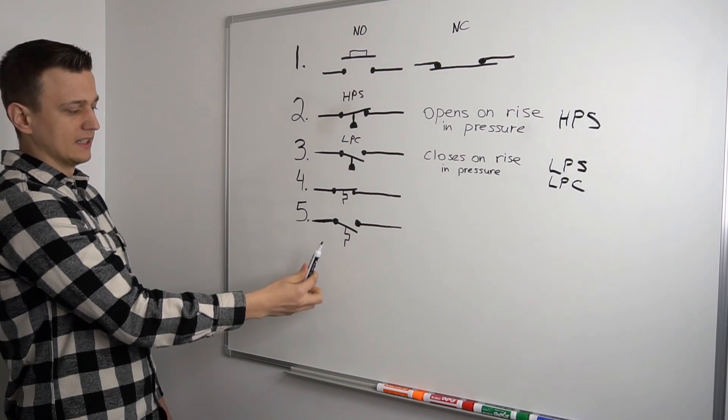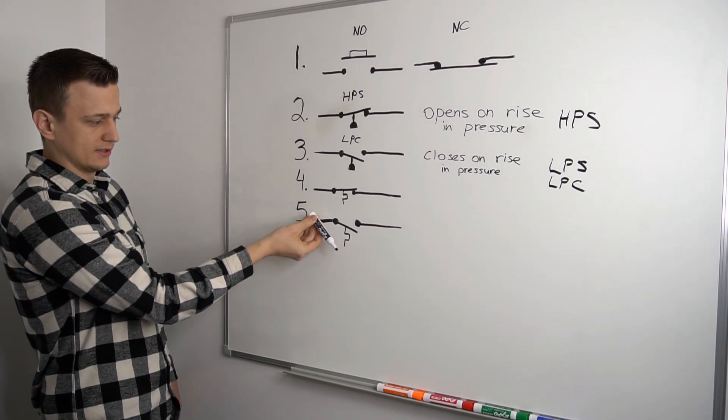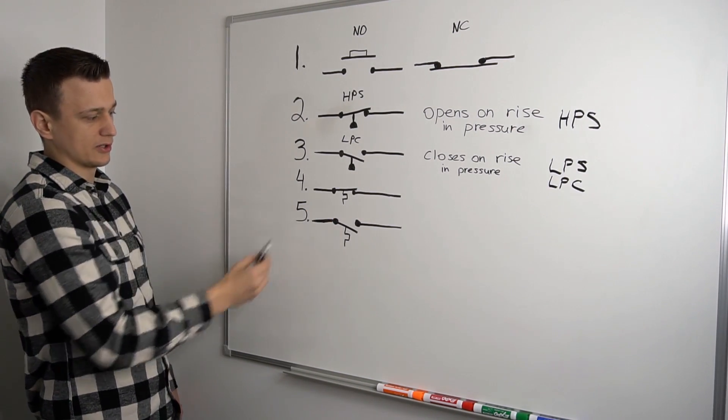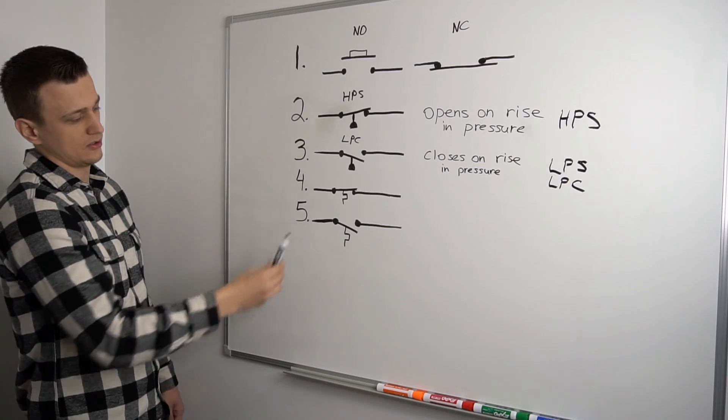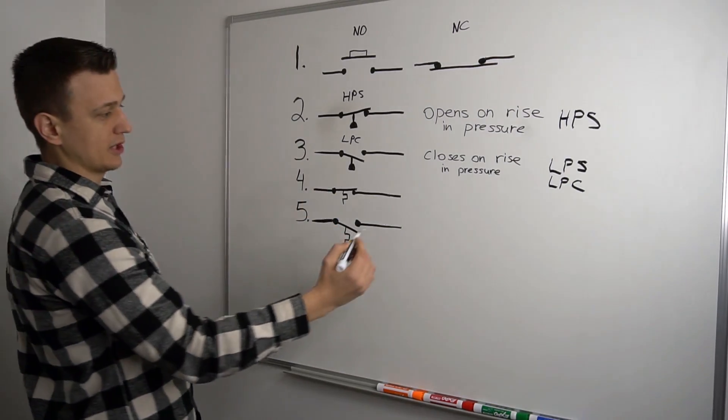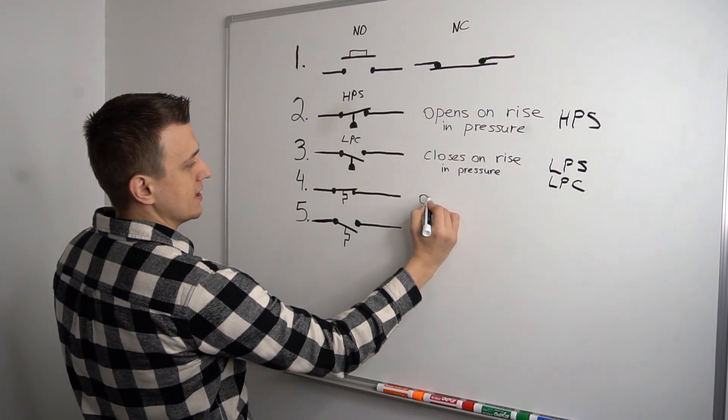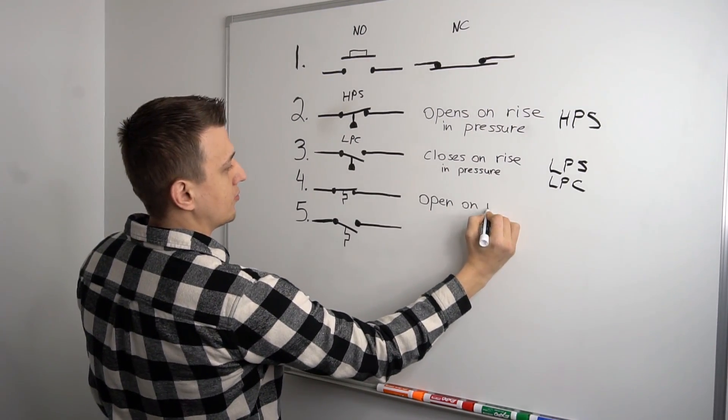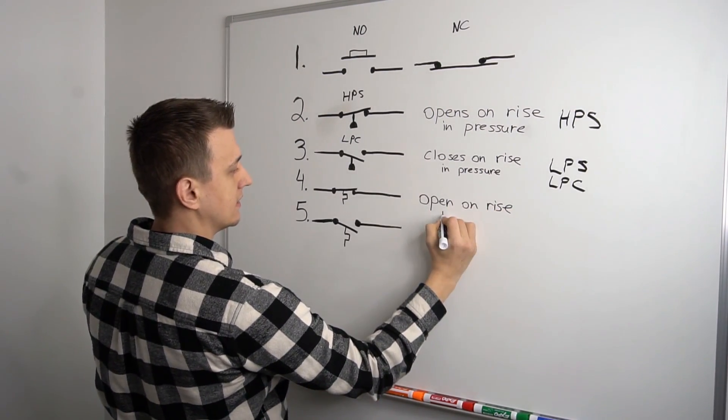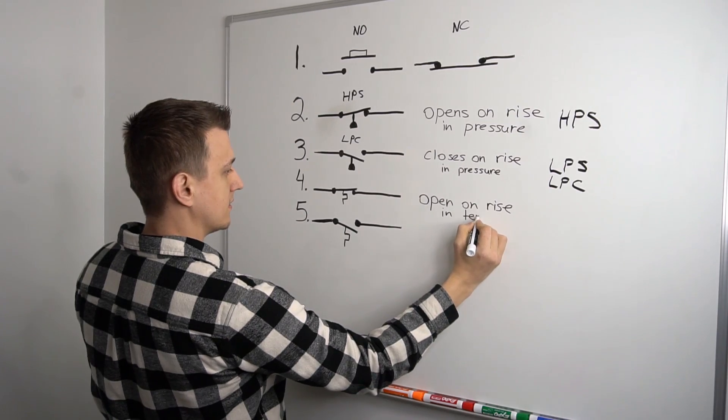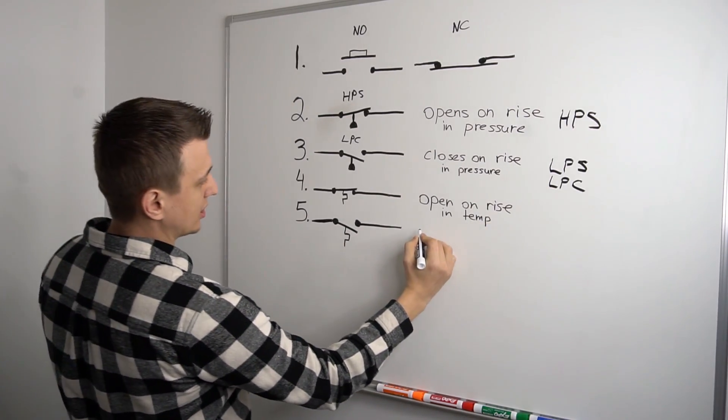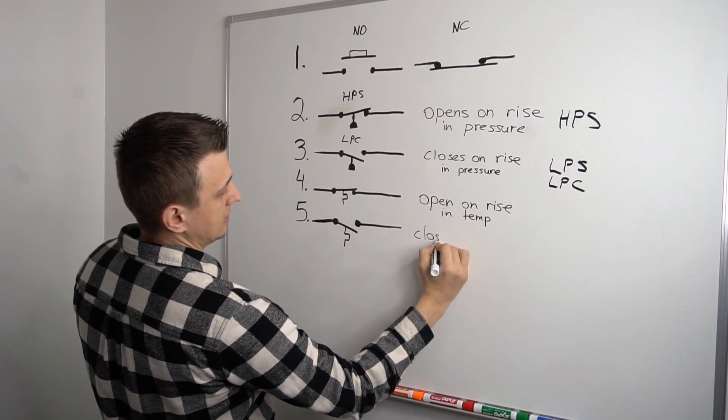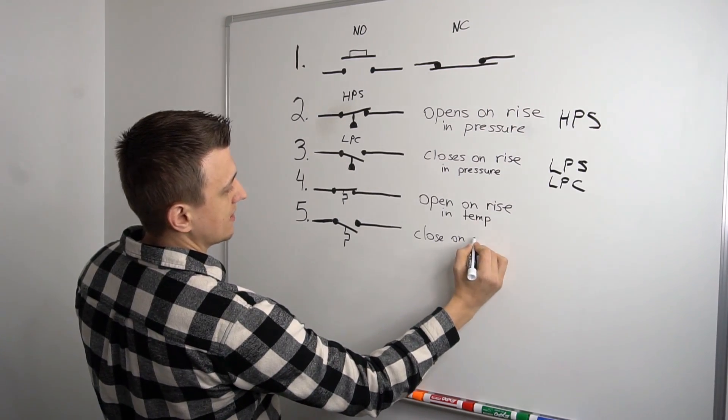So this switch right here is normally closed, but if it gets hotter than it's supposed to, this switch will open up and interrupt power. Whereas this one right here, if the temperatures go up, the switch closes and allows power to go through. So normally closed, normally open. And just like the pressure switches, this one would open on rise in temp. Whereas this one would close on rise in temp.